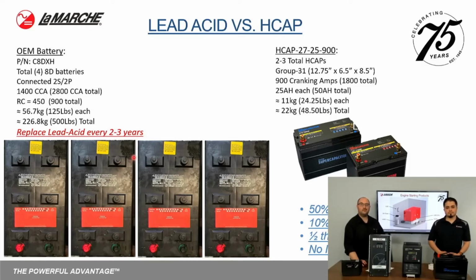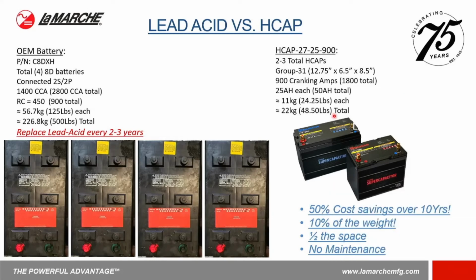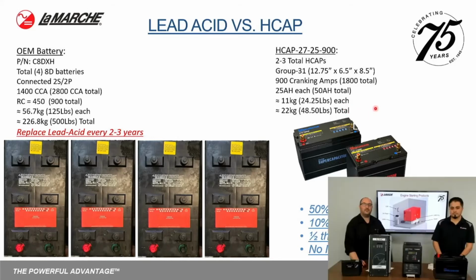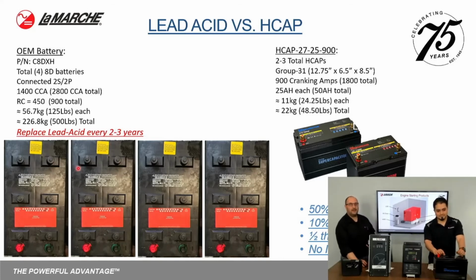years. Well, on the HCAP system, so much smaller, this one module that's being highlighted is a 24-volt module. I don't even need to series connect them. I just need to parallel as many as what's needed to meet the cranking and the energy requirement. So this is in a group 31 size case. They're under 50 pounds each. So keep in mind that on the lead acid battery, with that weight of 125, 130 pounds, OSHA is going to require 2 people to move those batteries.